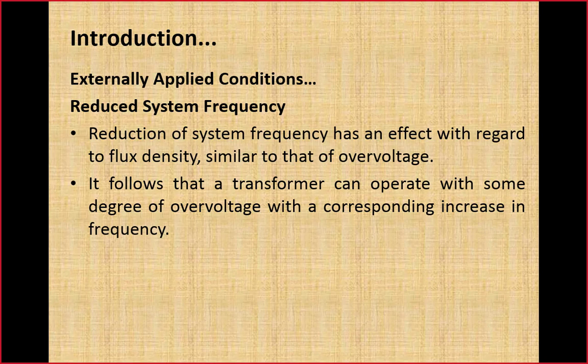So now here is another question that I want to address. A power transformer which is rated at 60 hertz frequency and some voltage. If we want to operate that transformer at 50 hertz, then remember its operation should also be done at slightly less voltage than its rating. How much less? So that the ratio of voltage to frequency remains the same.